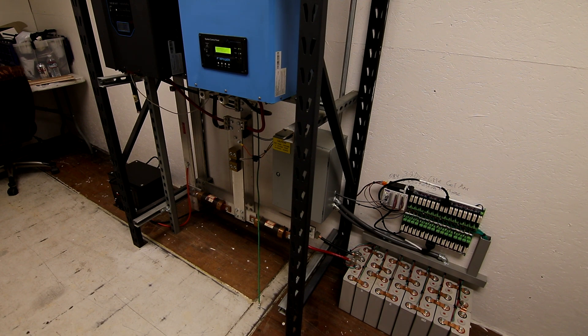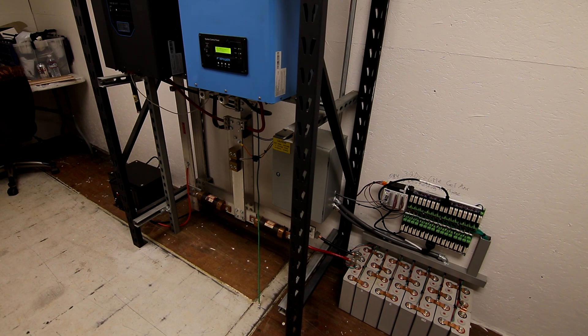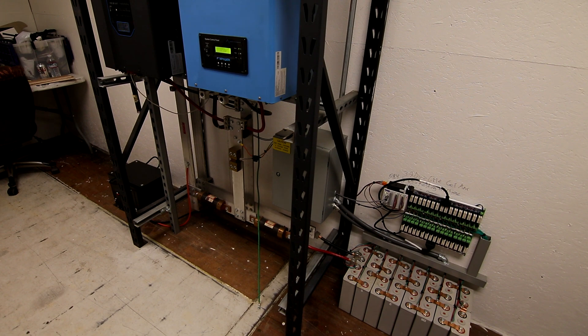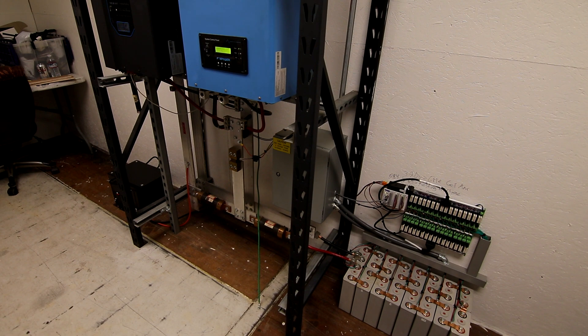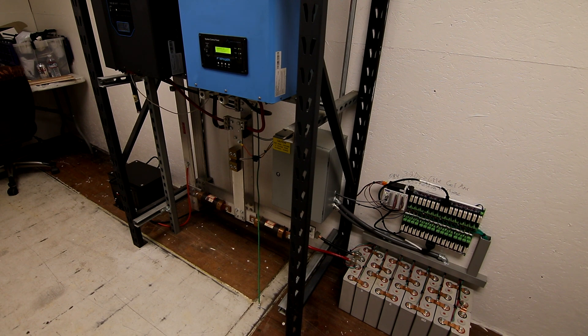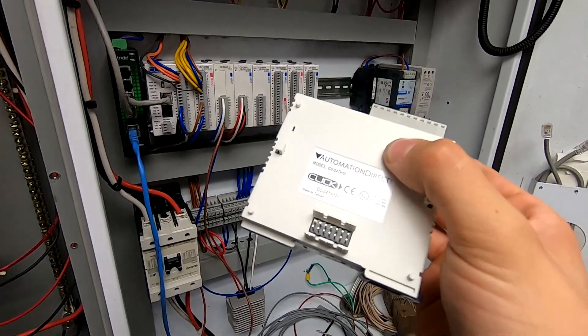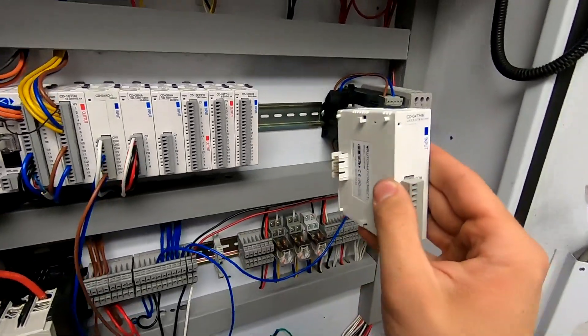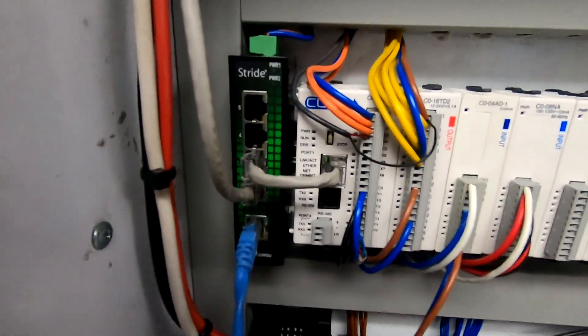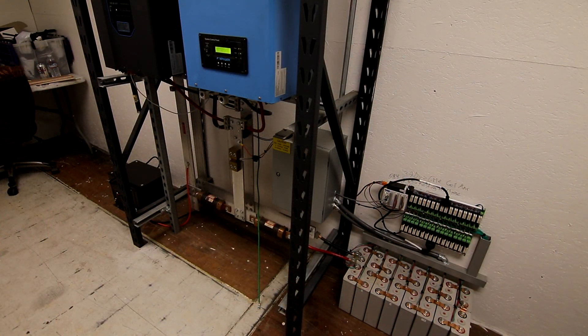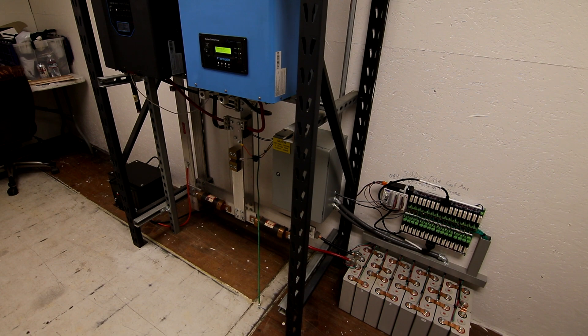I wish I had a couple more shunts so I could see how much power is going into my Fox power inverter as well as how much power is coming out of my battery charger but I really need to reconfigure these bus bars because I did install the shunt on the positive bus bar and typically you would install them on the negative bus bar that way the lines coming out of the shunt are common to ground so if you had a short to ground you wouldn't have the full capacity of the battery running through them. So when I install bigger batteries in here I'm going to make sure I get a couple more shunts and install them in such a way that I could monitor everything because some of you may remember a video, if I remember I'll put a card in the top corner, where I use a thermocouple module on my PLC to monitor these shunts and since they're a millivolt output and the shunts are a millivolt output they work very synchronous together and the results are very desirable.